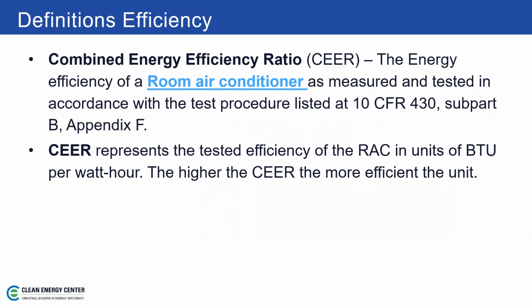So combined energy efficiency ratio, CEER, not to be confused with SEER, which we'll get to in a minute, is dedicated to describing the efficiency of a room air conditioner as measured and tested with the test procedure listed at 10 CFR 430, subpart B, appendix F. If you're interested, you can just plug that into your internet browser and pull it up. I'm probably the only person that would do something like that, but I always like to see what those test procedures include. CEER represents, at the end of the day, the tested efficiency of the room air conditioner in units of BTU per watt hour. So how many BTUs do we get out of it based on the amount of energy that we put into it in electricity? The higher the CEER, the more efficient the unit. So just remember, CEER is specifically for room air conditioners.